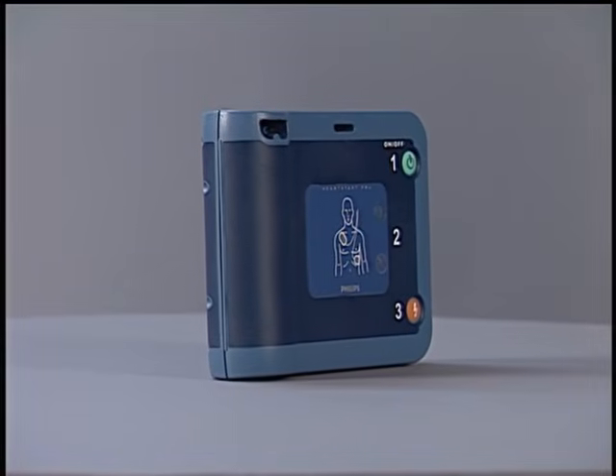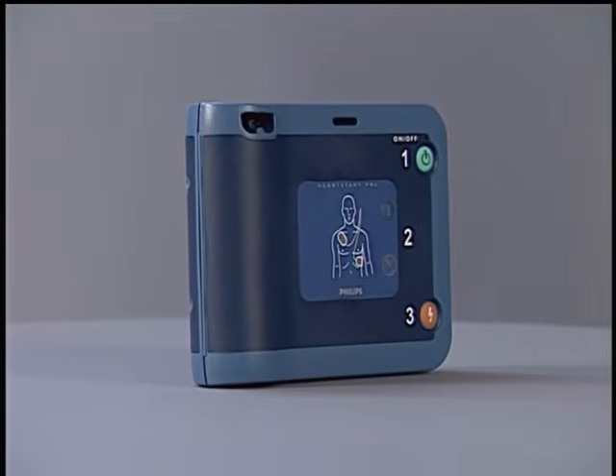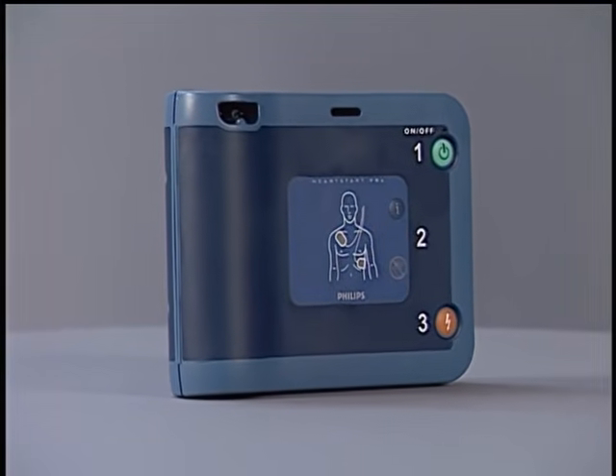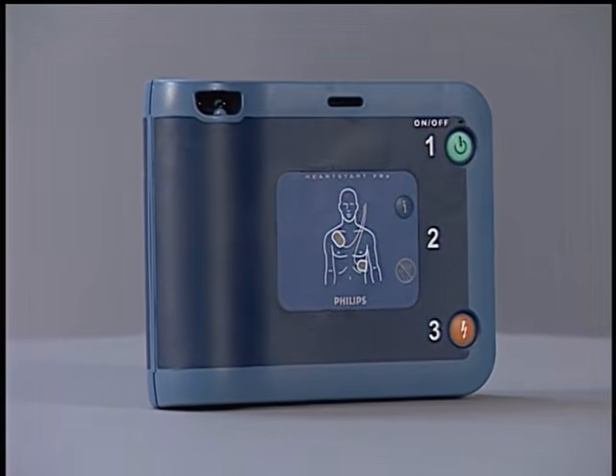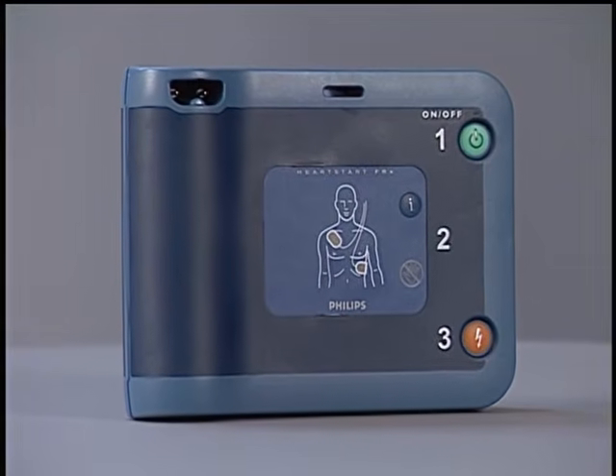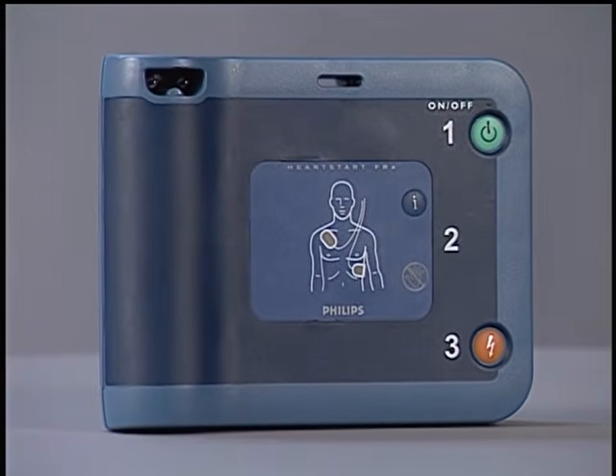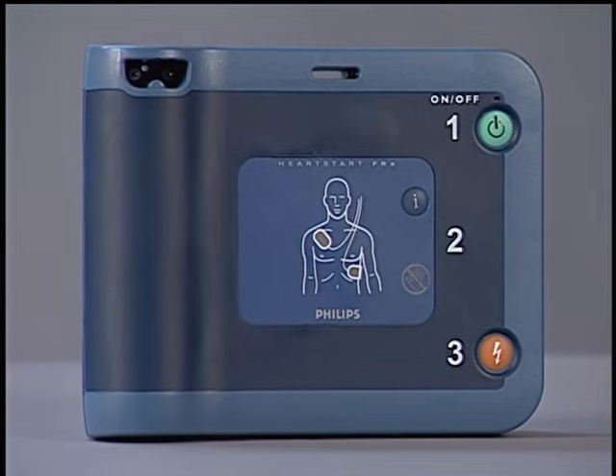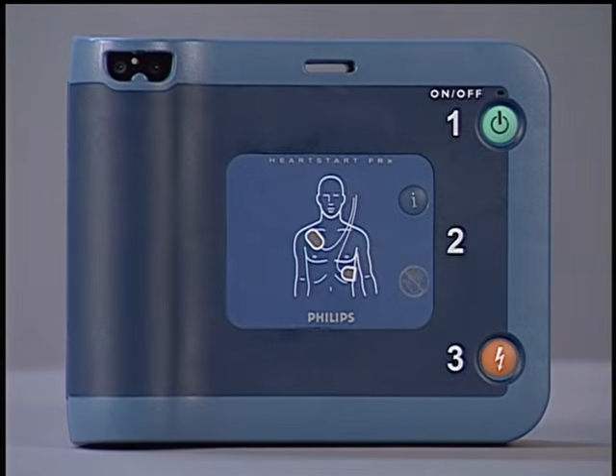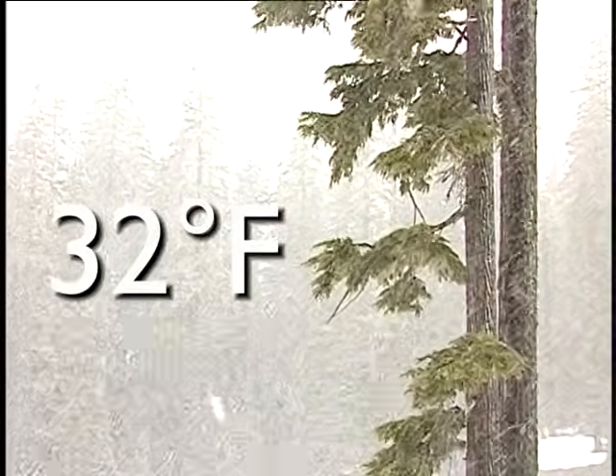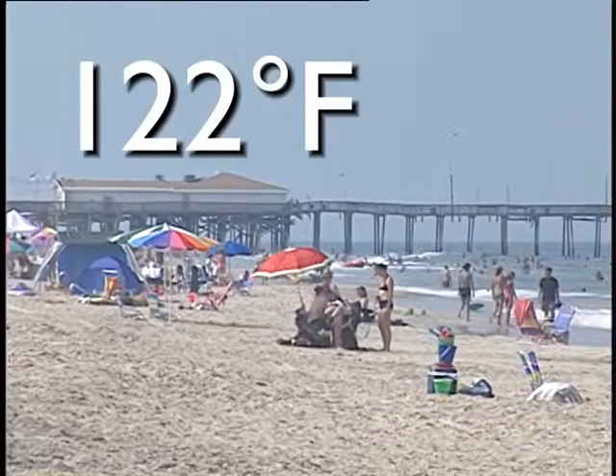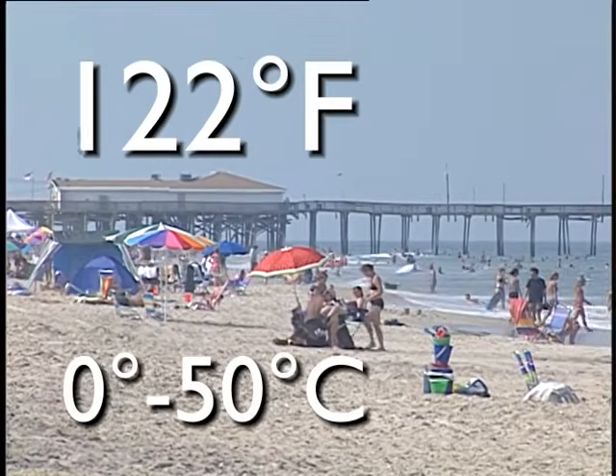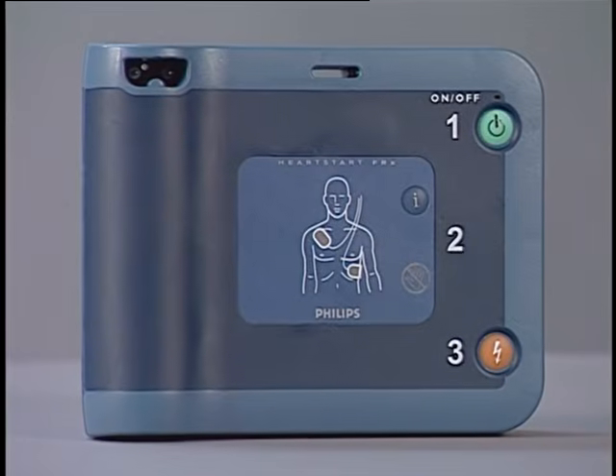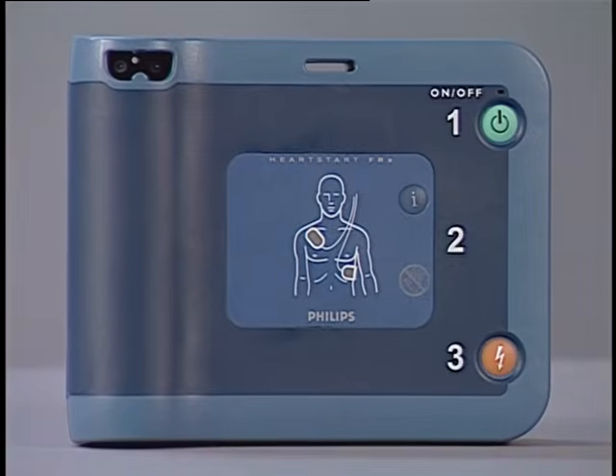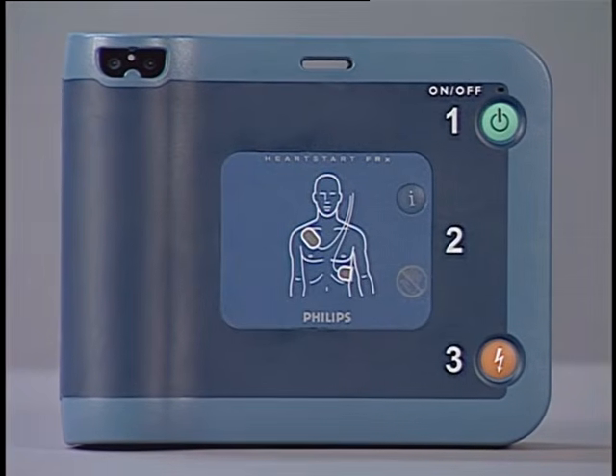With its long-life battery, Ready Light, and automatic self-testing, which also checks the pre-connected SmartPads 2, the HeartStart FRx defibrillator is virtually maintenance-free. It is designed to be tough and reliable in a range of environments. It can be stored and operated in temperatures between 32 and 122 degrees Fahrenheit, 0 to 50 Celsius. The FRx has no user-serviceable parts and should be returned to Philips in the event that service is needed.